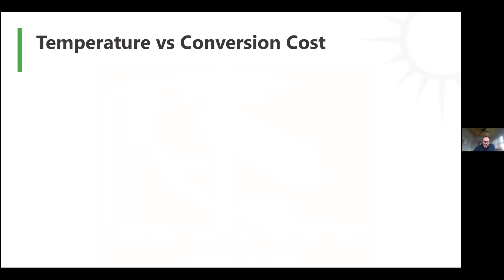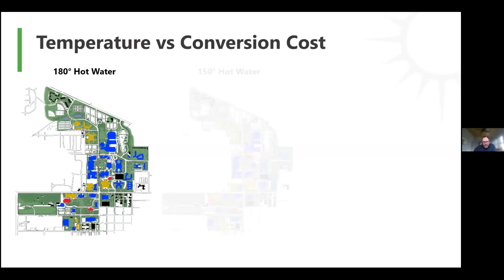At Ball State, we wanted to be careful selecting the hot water supply temperature. We looked at resetting the existing systems to 180 degrees, then 150, and even down to 130 degrees. You can see on this campus map that just setting back to 180 degrees triggered a couple buildings unable to maintain space temperatures—a modest number that could be easily addressed through conversion work.